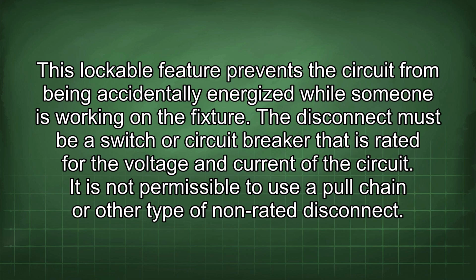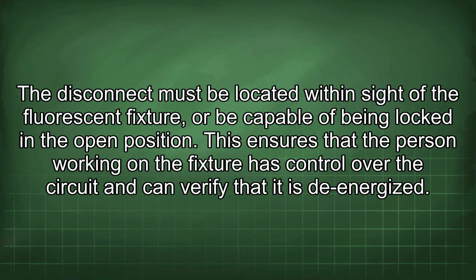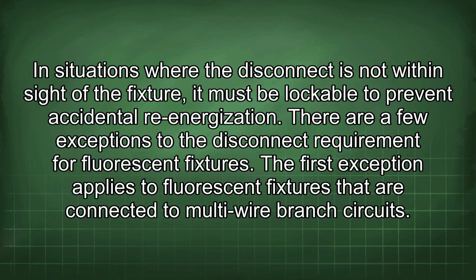The disconnect must be a switch or circuit breaker that is rated for the voltage and current of the circuit. It is not permissible to use a pull chain or other type of non-rated disconnect. The disconnect must be located within sight of the fluorescent fixture, or be capable of being locked in the open position. This ensures that the person working on the fixture has control over the circuit and can verify that it is de-energized.